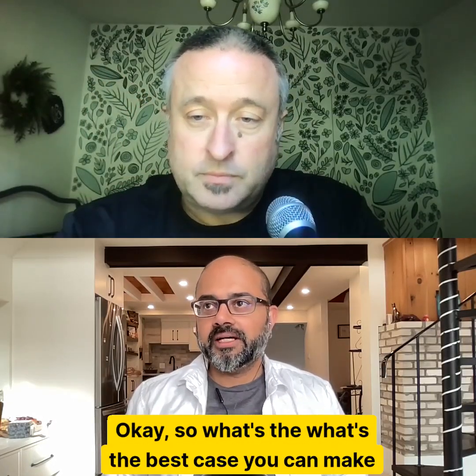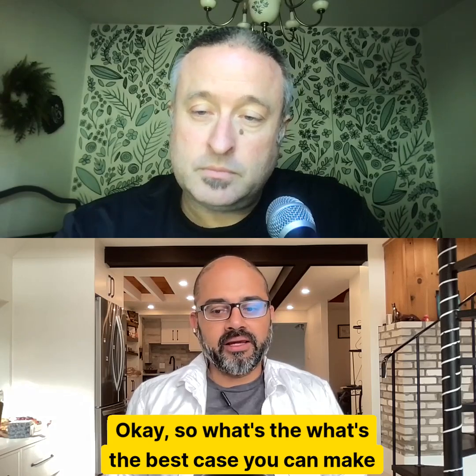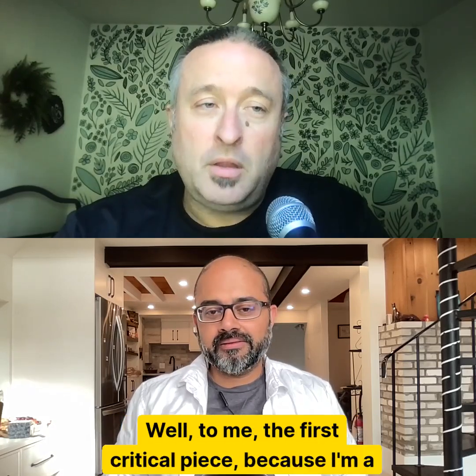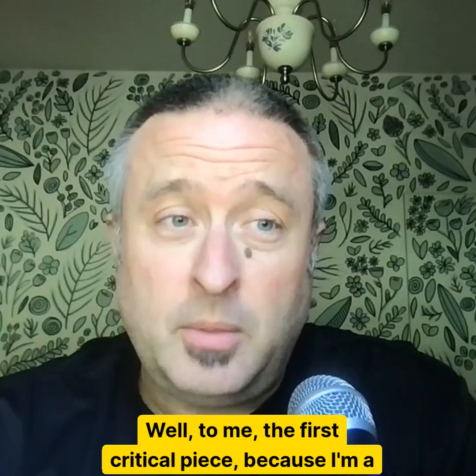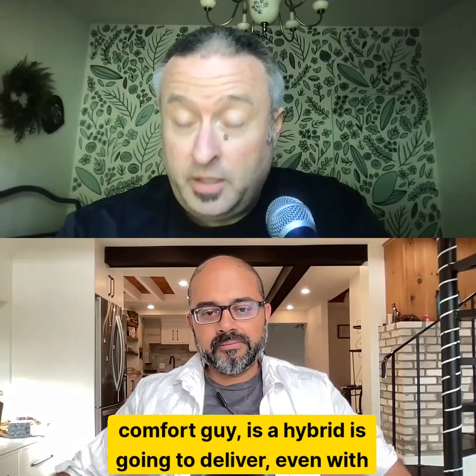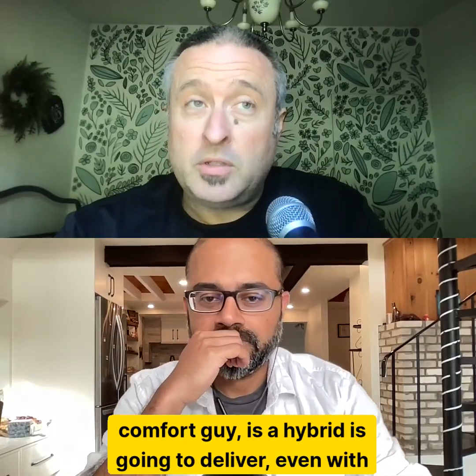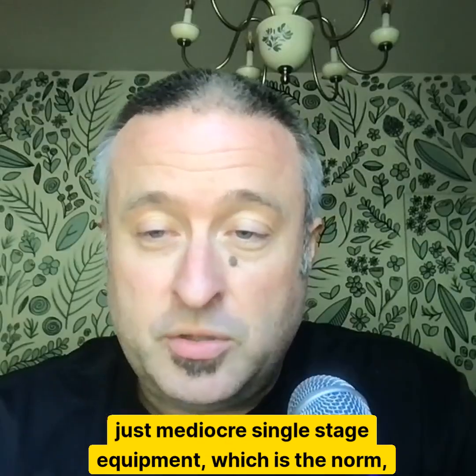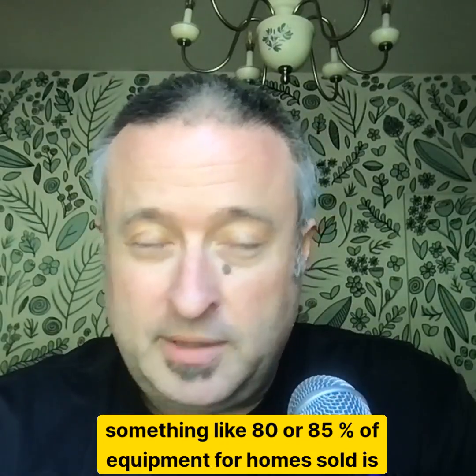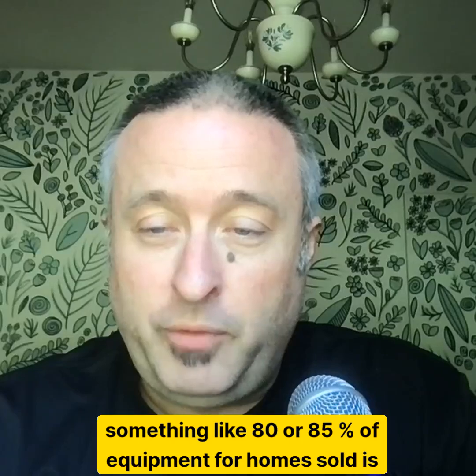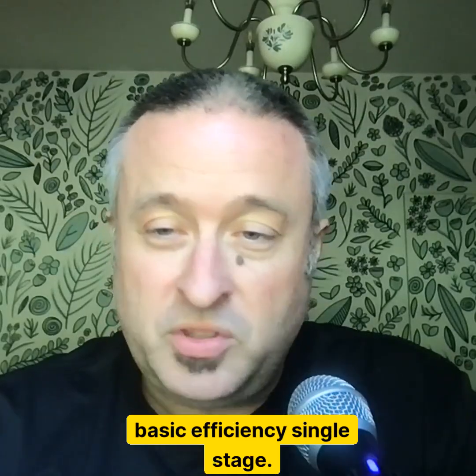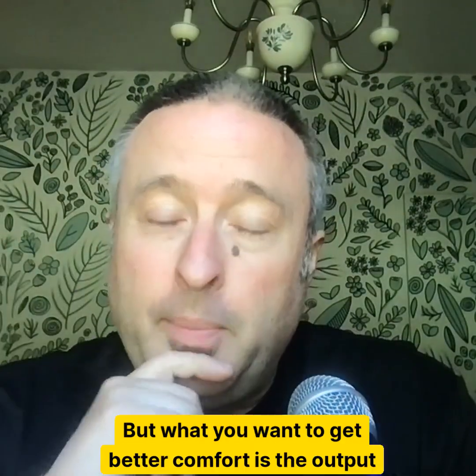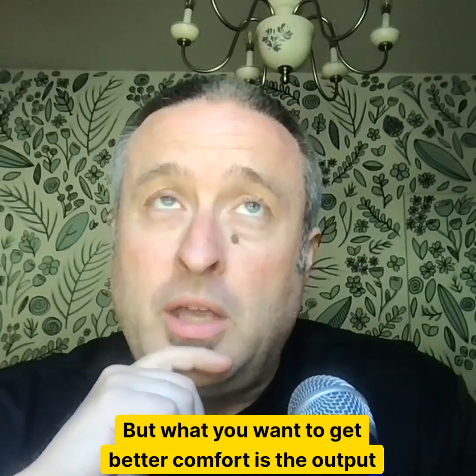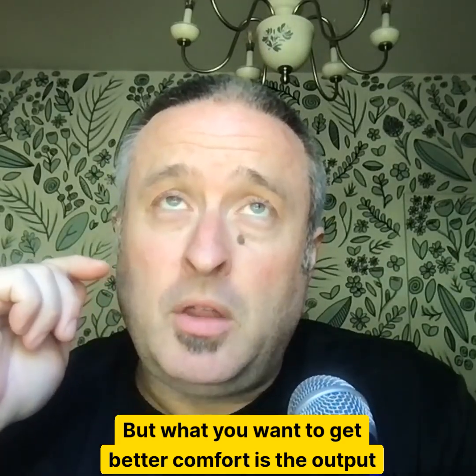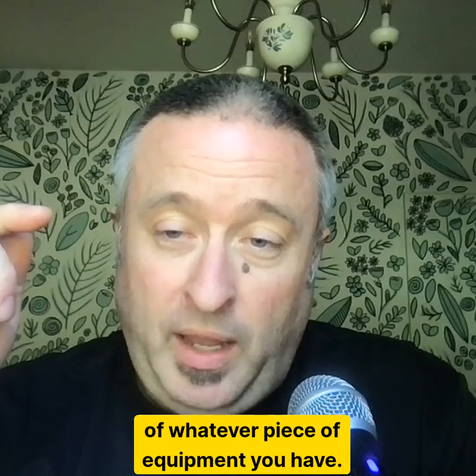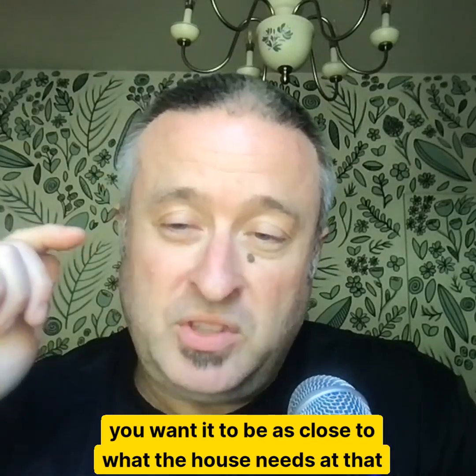So what's the best case you can make for hybrid heat pumps? Well, to me, the first critical piece—because I'm a comfort guy—is a hybrid is going to deliver, even with just mediocre single stage equipment, which is the norm. Something like 80 or 85% of equipment for homes sold is basic efficiency single stage, so it's on or it's off, there's no in the middle. But what you want for better comfort is the output of whatever equipment you have to be as close as possible to what the house needs at that moment.